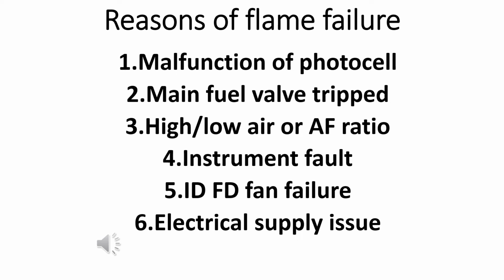Due to any issue to the ID or FD fan, if there is interruption of electrical supply to the motors of ID fan or FD fan. If ID fan or FD fan trip, then ultimately the burner management system gives the alarm of flame failure.